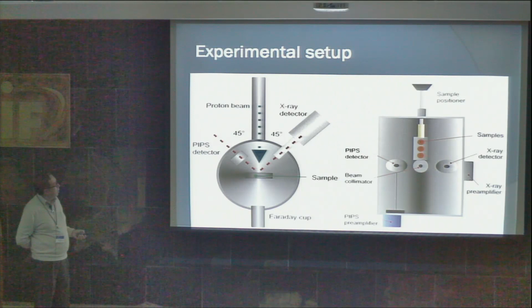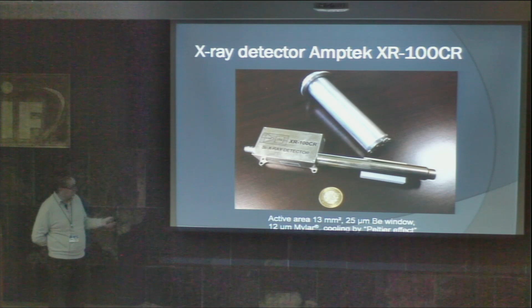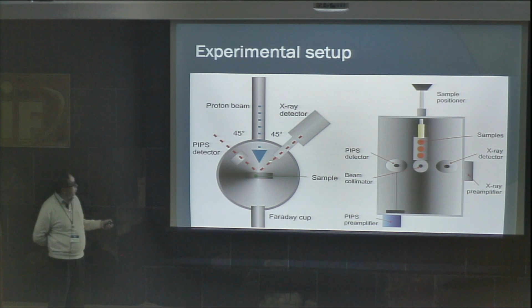In this case, we have a silicon PIN diode, which has an active area of 13 square millimeters, protected by a 25 micrometers beryllium window. We usually protect the detector with a 12 micrometers thick mylar film to protect it from backscattered protons or ions in general. It is cooled by the Peltier effect, an electronic process, so it needs no more liquid nitrogen. These are very small detectors. And we have here also our feed-through to insert this into the irradiation chamber. We connect this feed-through in this position.